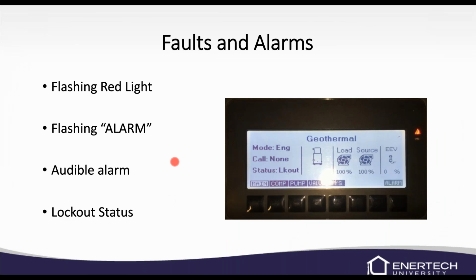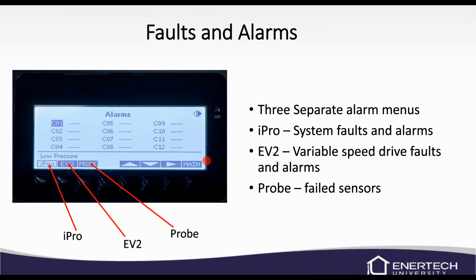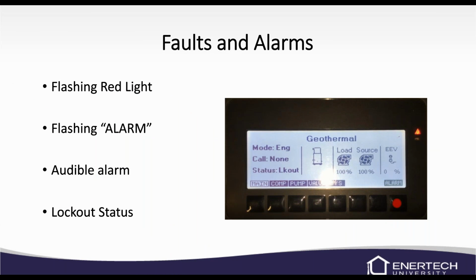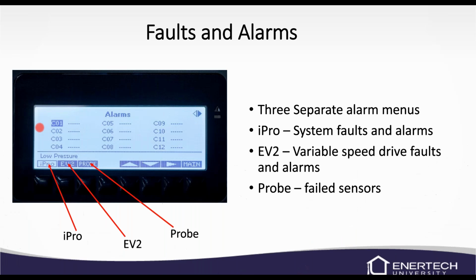Faults and alarms. If you have an alarm, in the right corner you'll see this triangle. In the field, it looks a little bit more red. Here, it looks kind of orange, but that's going to be on. There'll be an audible alarm that's beeping, and then you may see a flashing on the alarm button here on the screen, and your status will say lockout. If you need to get to the alarm menu, press the alarm button right here underneath the alarm, and that will take you to this screen here.